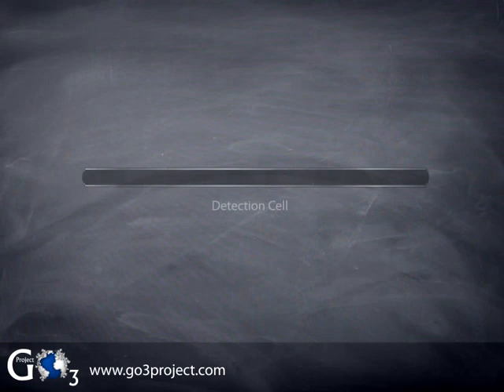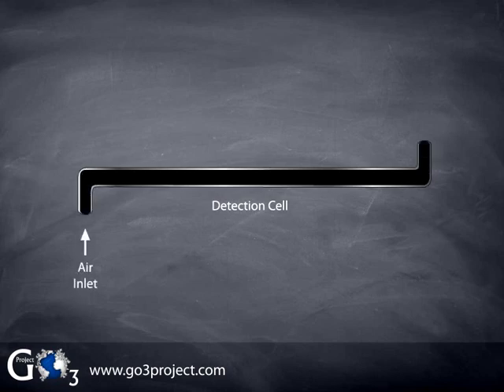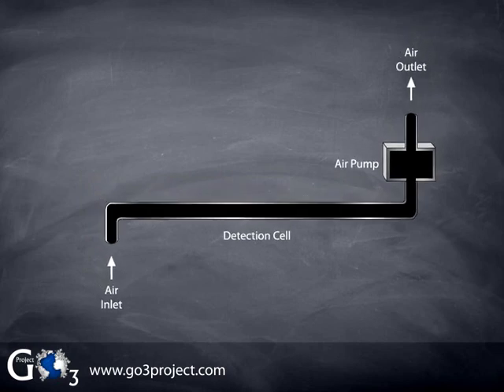To measure ozone in air, we start with the detection cell. This is just a quartz tube that we flow our sample air through. We need an inlet for the air to enter the detection cell and an outlet for the air to exit. Next, we need an air pump to draw the air through the detection cell. This pump works in the same way as an aquarium air pump, except that it uses suction to draw air through the ozone monitor instead of pushing it through.